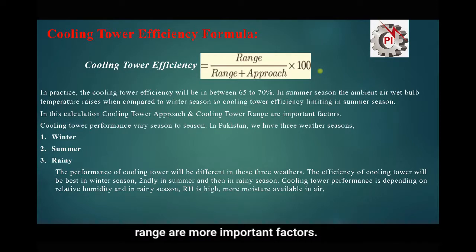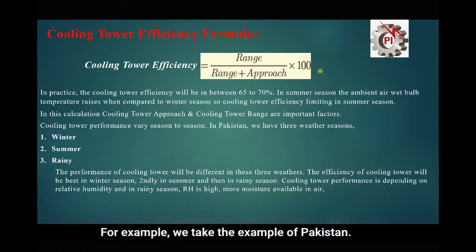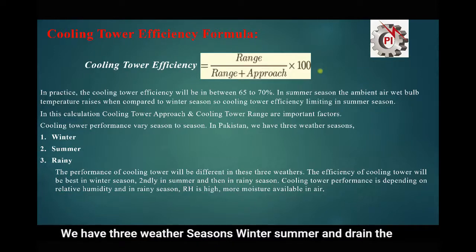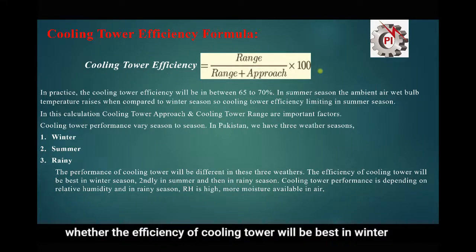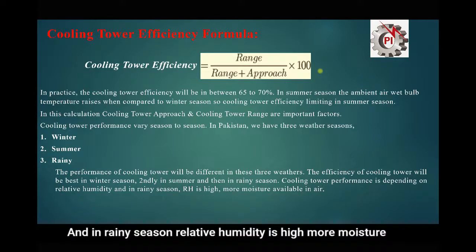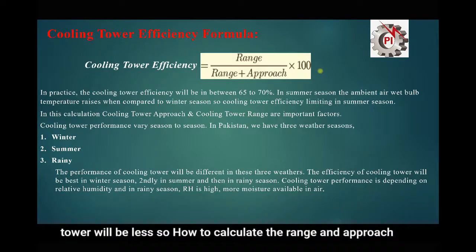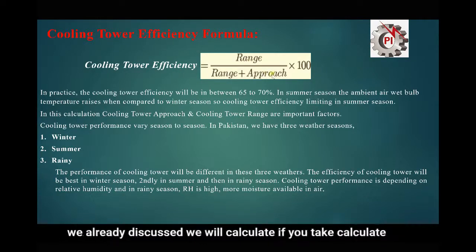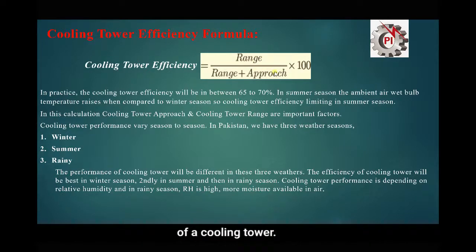Cooling tower performance varies season to season. Taking Pakistan as an example, there are three weather seasons: winter, summer, and rainy. The efficiency of the cooling tower is best in winter, second in summer, and lowest in rainy season. In rainy season, relative humidity is high — more moisture is available in the air — so cooling tower efficiency is least. By calculating range and approach and applying the formula, we can calculate the efficiency of the cooling tower. Thank you very much.